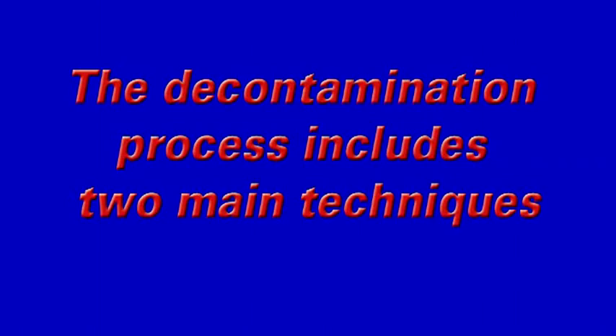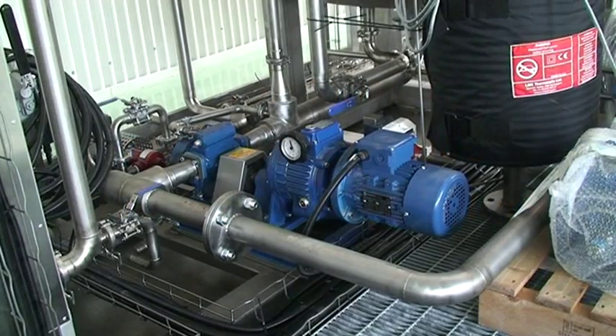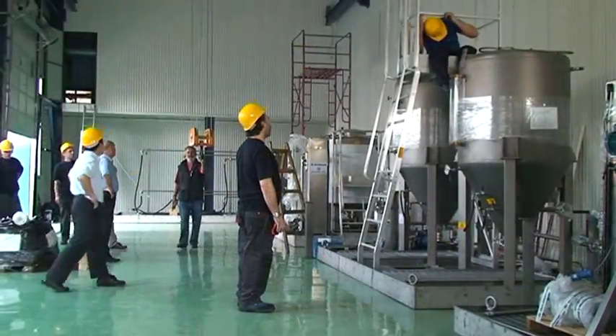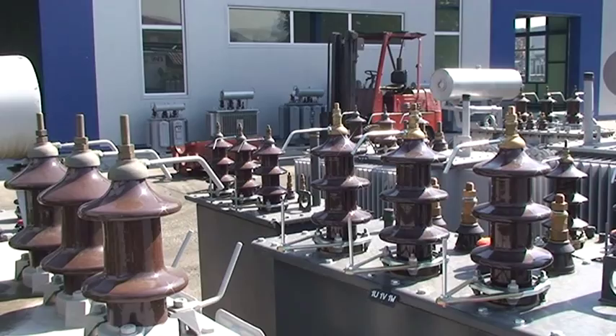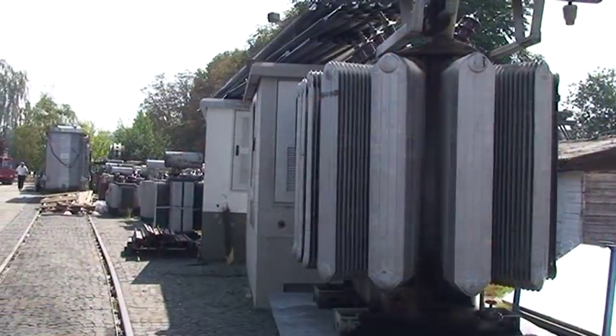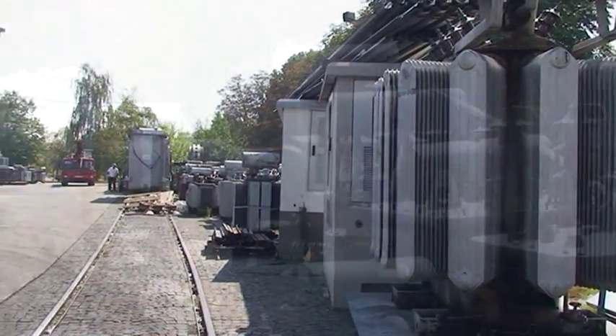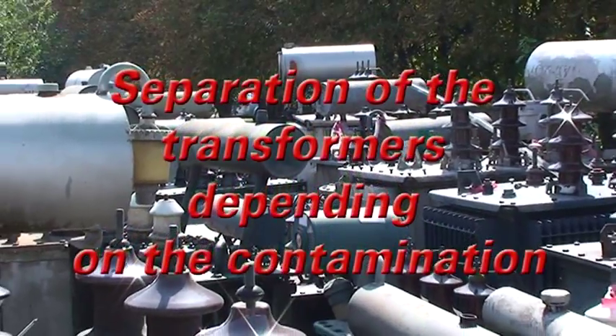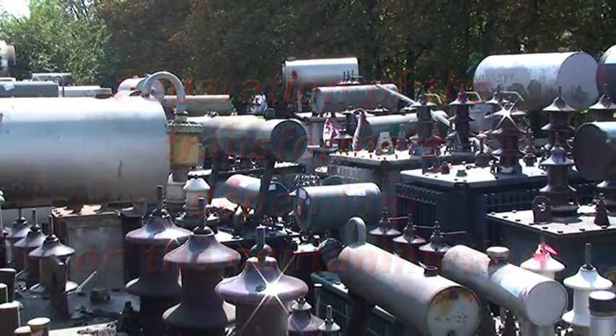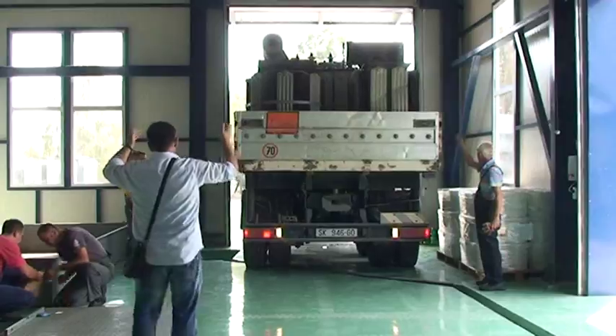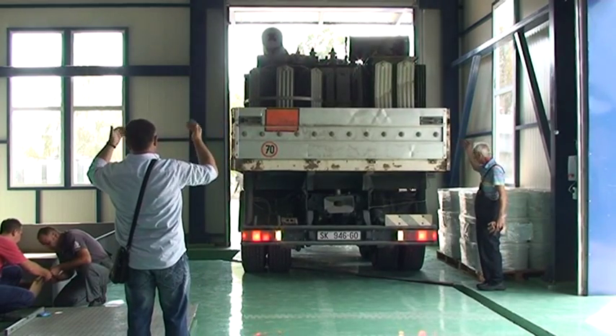The decontamination process includes two main techniques: dechlorination of PCBs containing mineral oil, and decontamination of metal surfaces and active parts. It includes the following phases: separation of transformers depending on the contamination. Depending on the contamination, the transformers are separated into different groups: high, low, and medium contaminant.